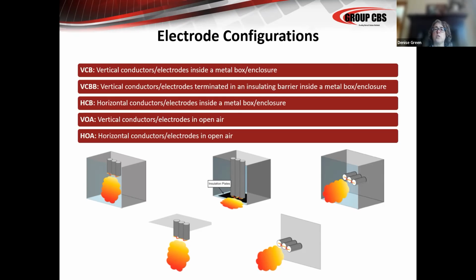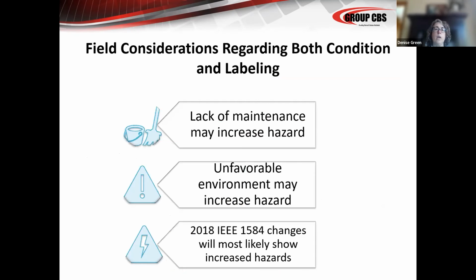Okay. So any question about conductors and electrodes? Okay, the field considerations regarding your labels. Always remember that the lack of maintenance of your equipment will generally increase your hazard. I put may, it's going to increase your hazard. The unfavorable environment may increase the hazard.